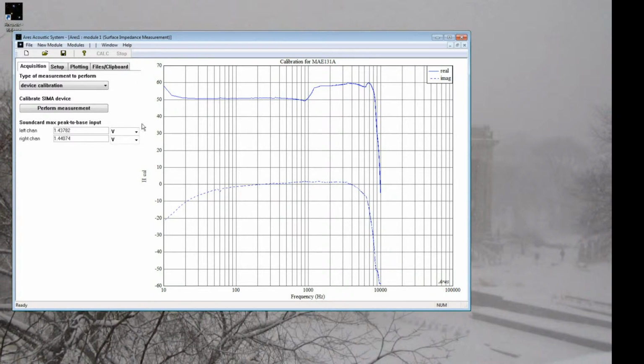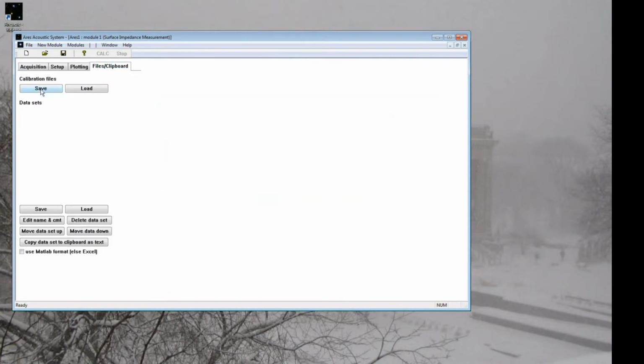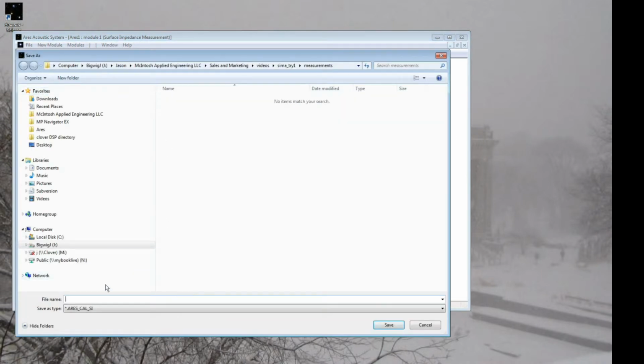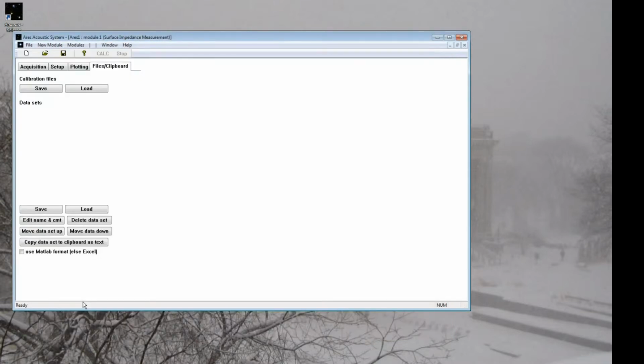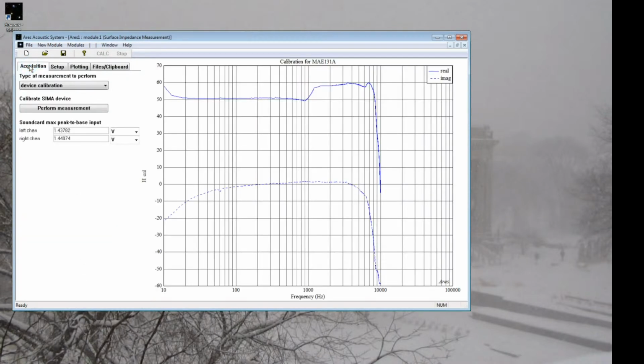When you calibrate a device, it's good to save the calibration data to a separate file so that you can have that later on. So we'll go to Files, Clipboard. Under Calibration Files, we'll hit the Save button, and I'm just going to type in MAE 131 here. It's good to put the date down so you know when you did the calibration. Also, as time goes on, it's nice to have a calibration history to see if the calibration has been changing over time. That might indicate that the device has become damaged at some point.